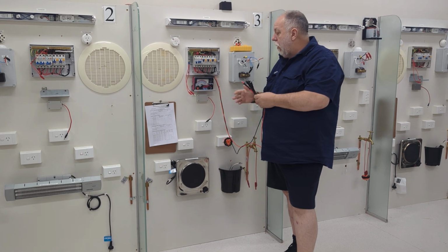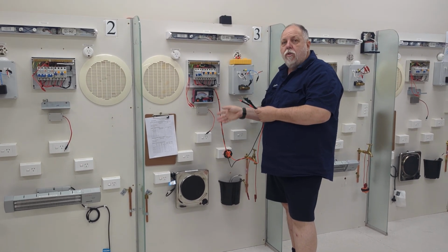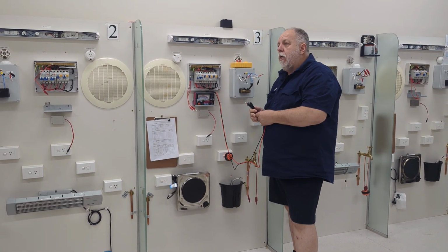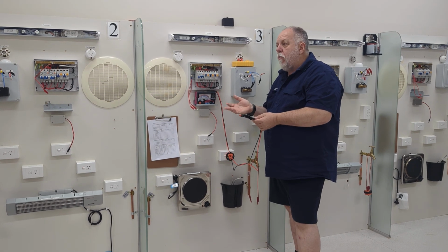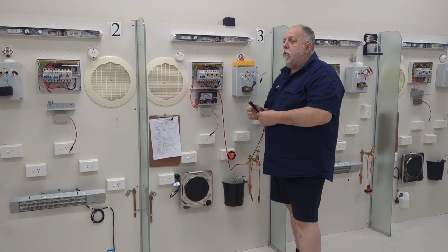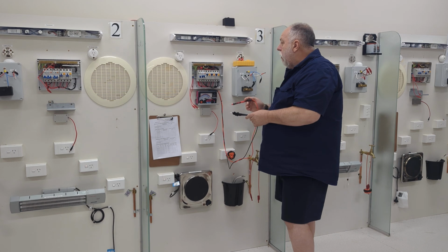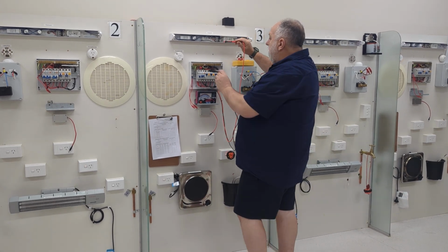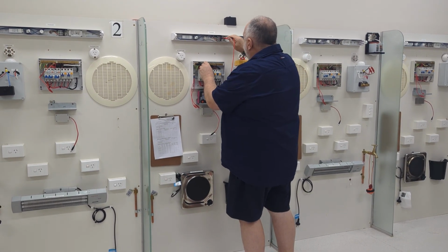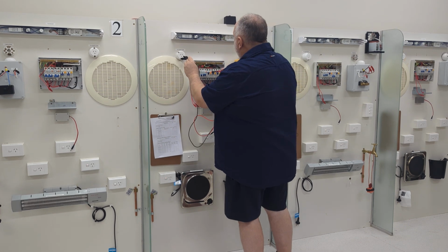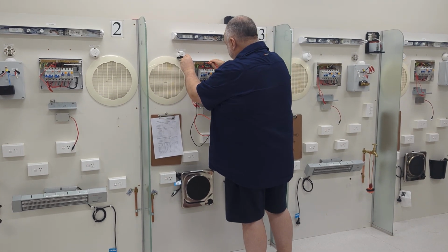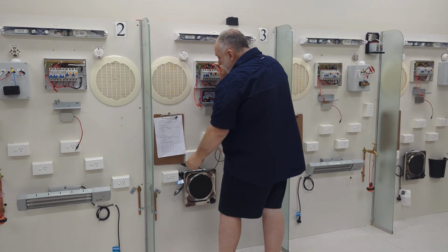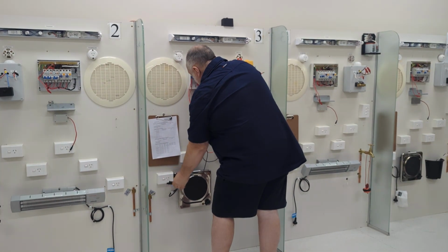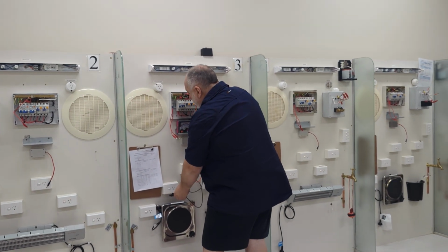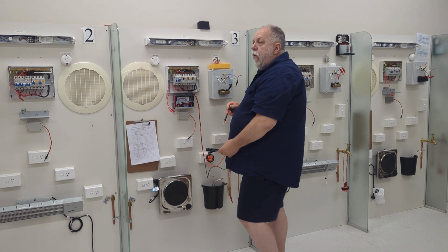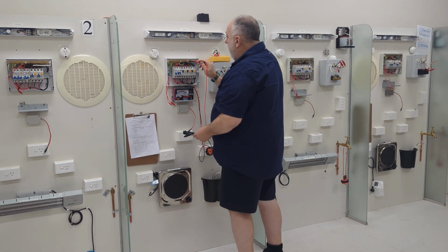Once we work out all the earth resistances, we then add them with the active. We go to our book, table 8.2, add the two together and see if it exceeds that value that's inside the book. So I'm also going to establish that all my earths are correct. I go from the earth bar over to here, beautiful, and I start working my way through all the earths. I get down to this one, beautiful. I got nothing here. So socket outlet number 3 doesn't have an earth. I can write that down.